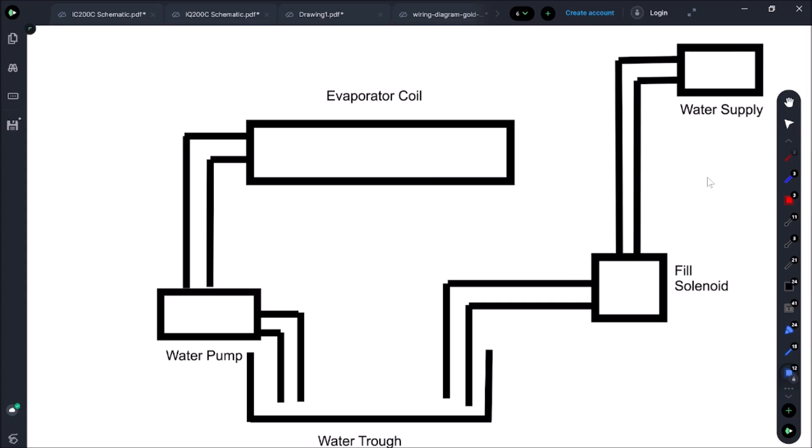How this water circuit works and how we're going to troubleshoot it. For ice machines I like to break it down into three circuits: water, electrical, and refrigeration. You'll usually find the problem is in the water circuit and if not it's in the electrical. It's very seldom that it's in the refrigeration circuit.